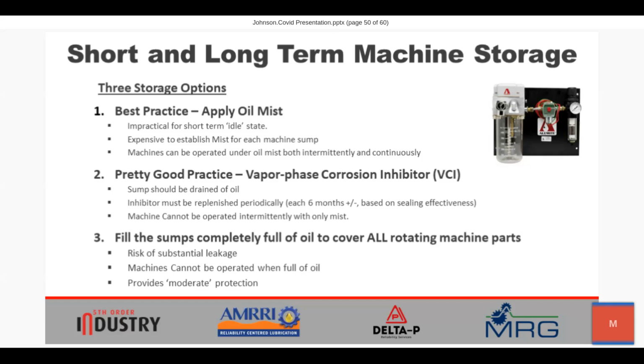The third option, which may or may not be practical, just depending upon your circumstances, would be to fill the sump completely with oil so that all of the surfaces, all of the rotating machine parts within that sump are underneath the oil level. Now, there is risk of substantial leakage to the shaft stub points for any housing where we do this. The machines cannot be operated when they are full of oil. They cannot be turned over by the electric motor.